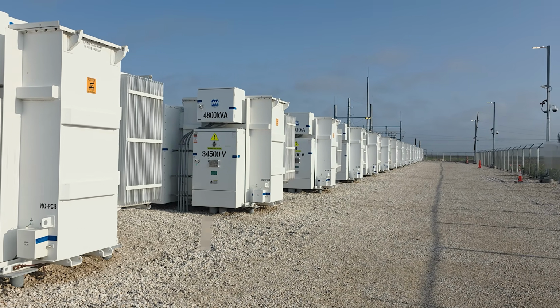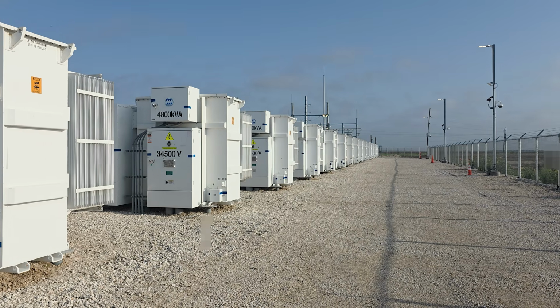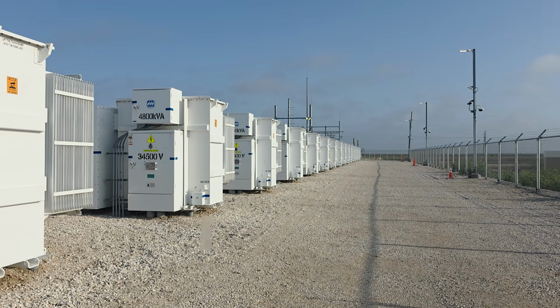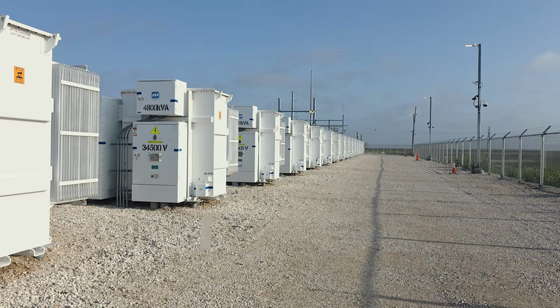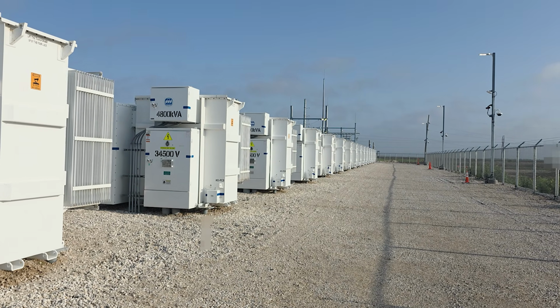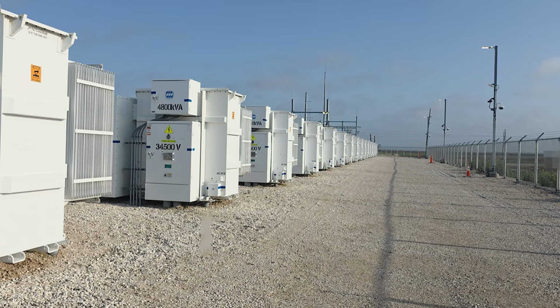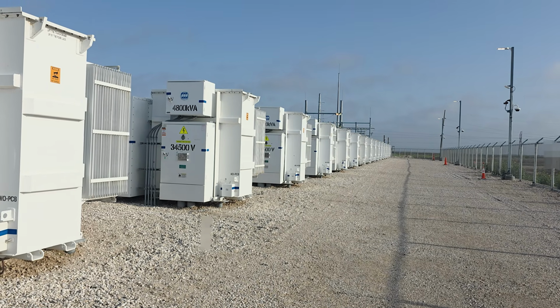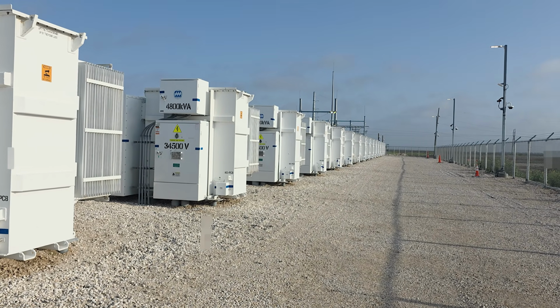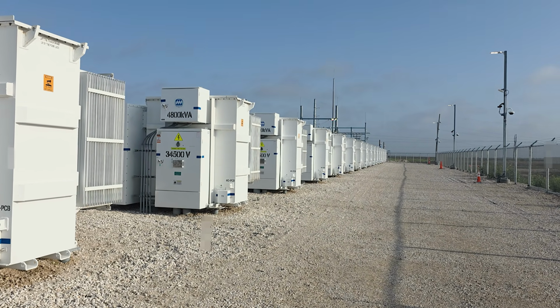What's interesting about the substation is this is the first time I've seen a substation with no local control, zero. You cannot open a single breaker or close anything. It is all done remotely, 100%. That's the first time I've seen that. So there are no switches, there are no buttons. It's all servers and relays and nothing else. So they've got a remote center that will operate these.